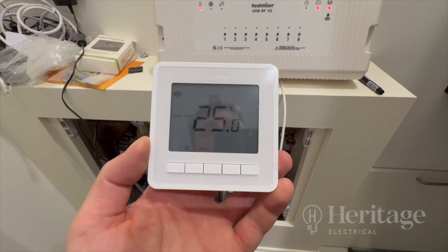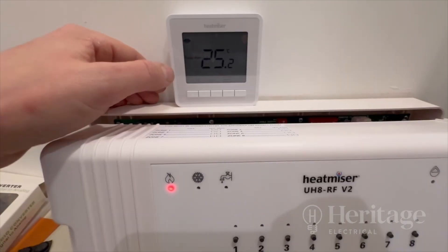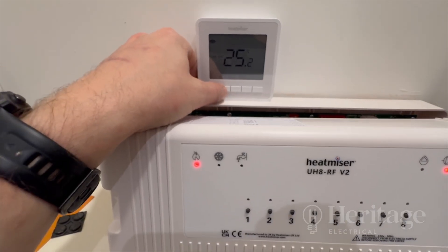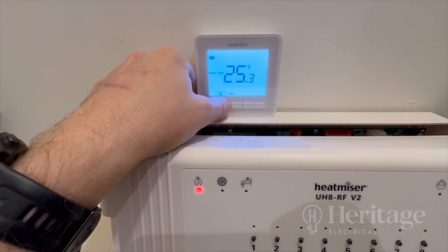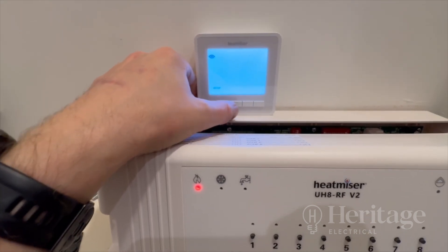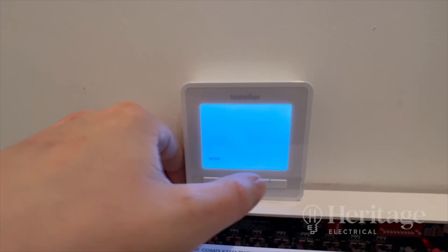I'm going to pair the thermostat to the relevant zone — zone one on here. You have to highlight the power button, push and hold that for three seconds. Set-ups is highlighted, push the tick.